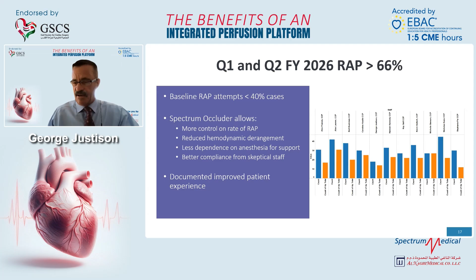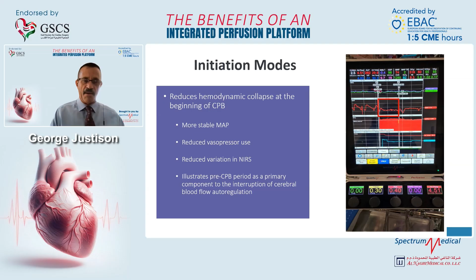The initiation mode helps us to reduce the hemodynamic collapse at the beginning of bypass because we can now program a very specific flow rate that we initiate bypass at over a specific time period. So it allows for a more controlled transition from patient's cardiac output support to the heart-lung machine. So as a result, we see more stable mean arterial pressure, reduced vasopressor use, and reduced variation in NIRS. As a matter of fact, you can see in the pre-bypass period here where there was a lot of cyclical nature in the mean arterial pressure. This is during the anesthesia support prior to bypass, to a much more stable initiation and cardiopulmonary bypass.